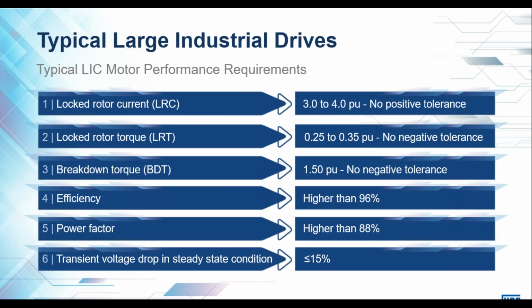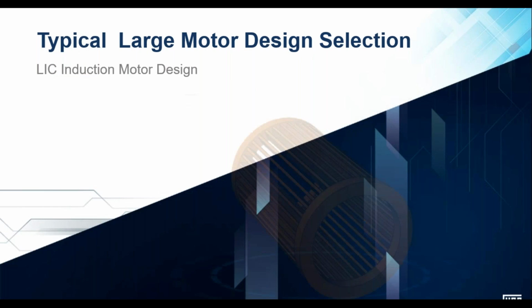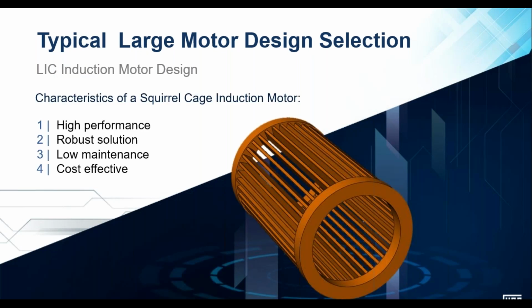From an efficiency point of view, we're aiming for, on these large motors, typically more than 96%, power factor more than 88%, and as mentioned, a transient voltage drop in steady state condition of 15% or less. So in essence, we want to design a motor that has a lower starting current, but we want to maintain the performance advantages of a normal squirrel cage machine, and that is high performance, robust solution, low maintenance, and keep it cost effective.